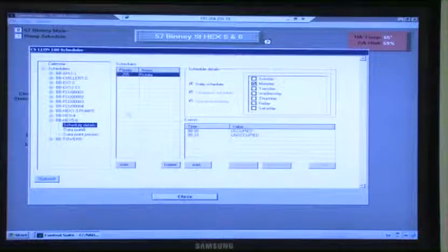Schedule details. Rotate daily schedule Monday. So every Monday it changes. Okay. That 3-minute differential between the two is just to give it a pulse and then back it off again. But at 8:30, it's going to swap. If we don't like this, we can go in and change it anytime. I was just curious how often they rotate.